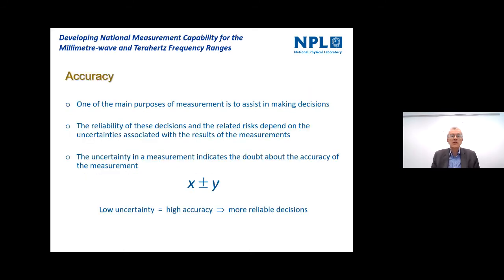So for accuracy, as you remember at the outset, I said one of the main purposes of measurement is to help us make decisions. And really the reliability of those decisions and related risks depends on the uncertainties in the results of the measurement. So typically we show uncertainties, as I've shown you there, as x plus or minus y, where the y is the uncertainty in the measurement, and gives us an indication of the amount of doubt we have about the accuracy of the measurement value x. So for example, if the uncertainty is low, if that value of y is small, then that implies we have high accuracy, and that means we can make more reliable decisions, both scientifically and commercially. So it's very important. I do have to emphasize that the plus or minus y symbol can also be used for other things.